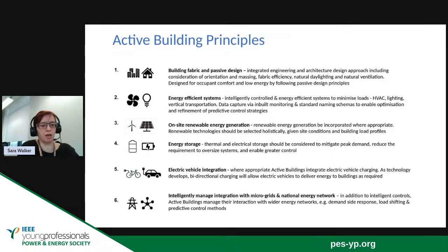Air-to-water heat pumps, which are pretty typical for smaller commercial units and for homes, have coefficients of performance of between 2 and 3, depending upon the external temperature. It varies throughout the year. So we've got very energy efficient heating, ventilation and air conditioning design in the building.